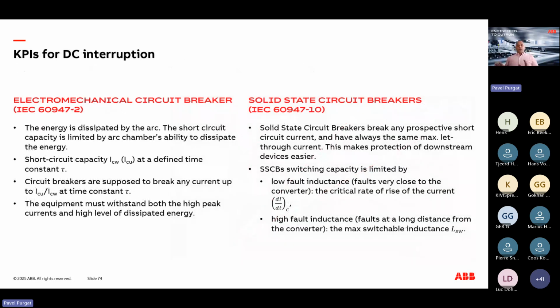Now, if this time is too long, what can happen is that the breaker will no longer be able to safely interrupt the current. So when we compare the two breakers, or the two technologies, because we need both at the end of the day, the electromechanical circuit breakers are limited by their short circuit capacity, while solid-state circuit breakers are limited or defined by the amount of inductance in the system. If it's too low, then it can happen that the breaker is not able to interrupt fast enough. If it's too high, the energy that needs to be dissipated in the circuit breaker can be too much. So this is something to also give a perspective that one is not replacing the other, rather they are just complementing each other, and we need both technologies.